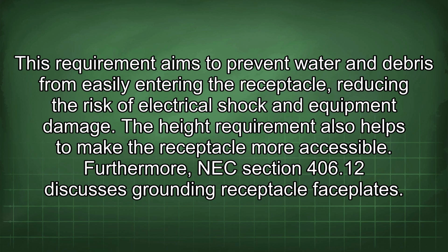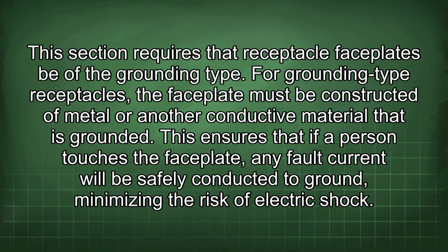Furthermore, NEC Section 406.12 discusses grounding receptacle faceplates. This section requires that receptacle faceplates be of the grounding type. For grounding type receptacles, the faceplate must be constructed of metal or another conductive material that is grounded.